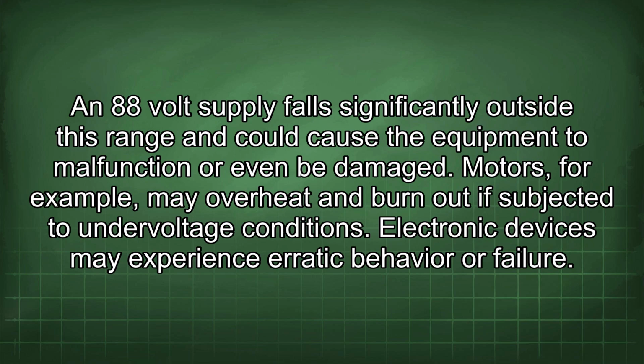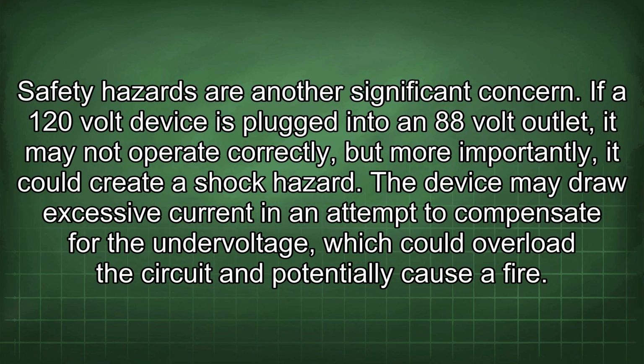Motors, for example, may overheat and burn out if subjected to undervoltage conditions. Electronic devices may experience erratic behavior or failure. Safety hazards are another significant concern. If a 120 volt device is plugged into an 88 volt outlet, it may not operate correctly, but more importantly, it could create a shock hazard.